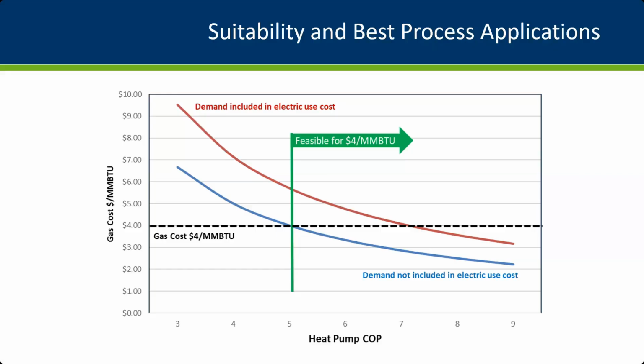When we look at gas and electric costs and their ratio, this graph shows that depending on the electric costs and whether demand charges will be impacted by the heat pump, the required COP can be established based on prices for the site. If demand is not included in the electric cost, a lower heat pump COP would be cost effective, whereas if there are demand charges, a higher heat pump COP is needed.